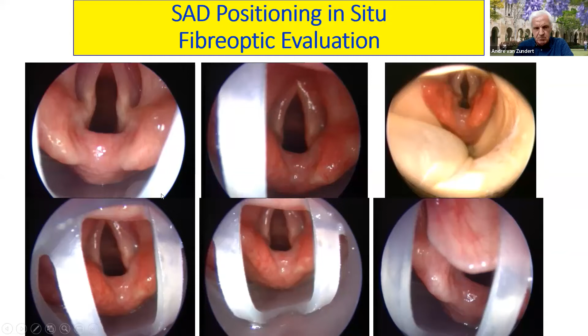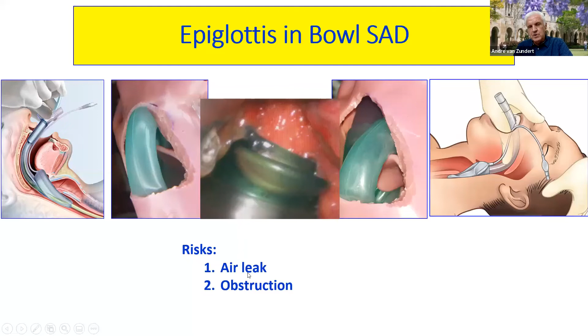Whereas with fiber optic evaluation, we want to see the full POGO, the percentage of glottis opening, which in this particular area is 100%, 100%, 100%, as you can see in here. Whereas this is not so good because the epiglottis sits now in the bowl of the device, partially obstructing, and it can even cause complete obstruction. The mask aperture bars were designed to prevent epiglottic downfolding, but we have proven in other publications that the mask aperture bars have no meaning whatsoever, so they should not be included as in this particular case. So air leak can be the result, as you can see here, or complete obstruction, as in this particular case. So we need to do something better.